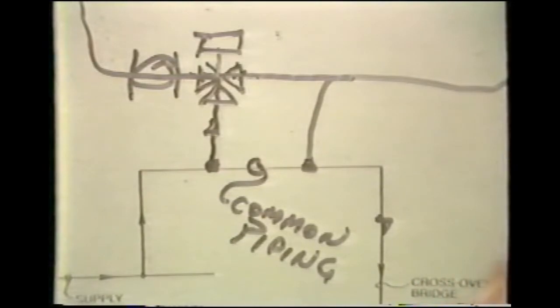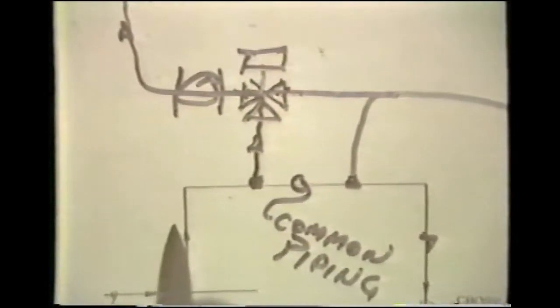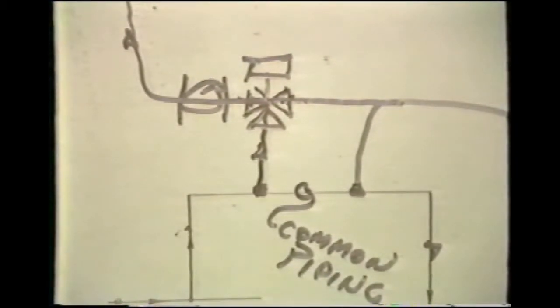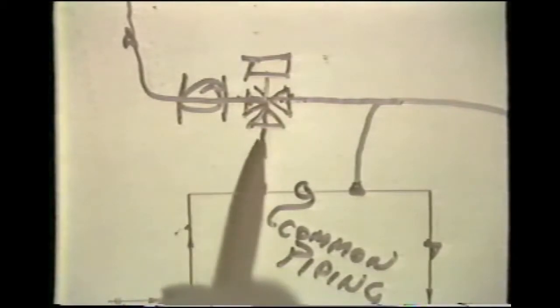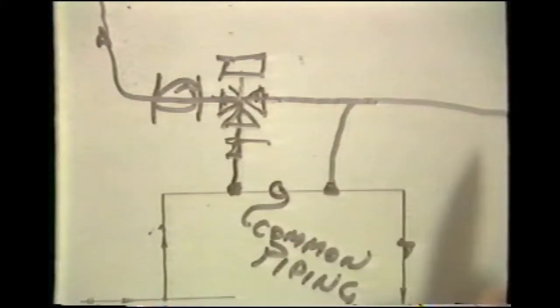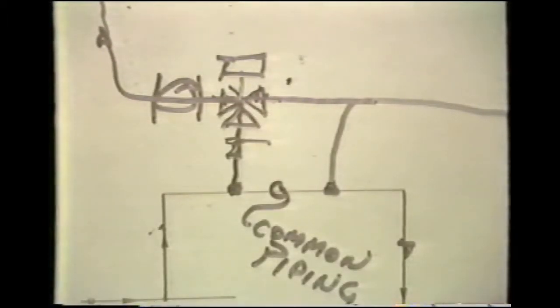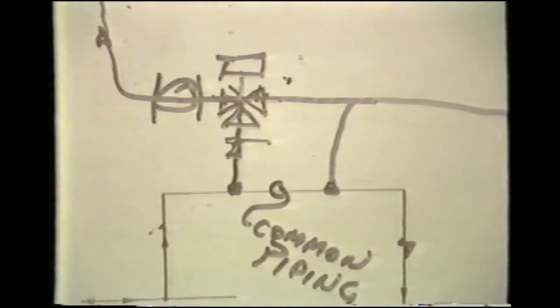The other statement was this, that many times the secondary circuit pipe size was considerably greater than the pipe size used in the crossover bridge line and for the inlet bleed line into the bottom of that control valve. This made the three-way valve act rather as a sewer in terms of the flow it was attempting to control, and led to some difficulties because of the oversizing of that valve relative to the actual distribution system. So let's change that and illustrate the changes that occurred once this was developed.